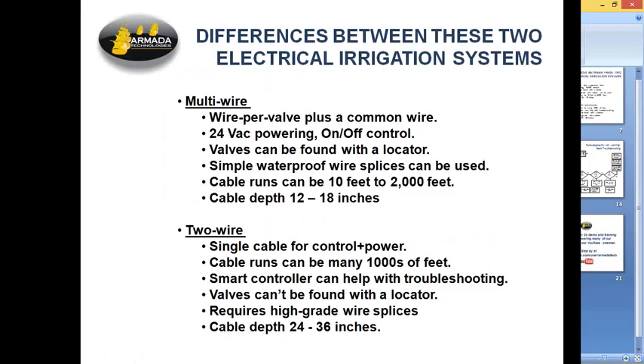The multi-wire turns on valves with a shot of 24 volts AC, and the two-wire systems commonly have something over 30 volts running on their control cable, and that voltage is led out to the valve to close the valve based on the command to a decoder. So literally, when you start working on two-wire systems, you're becoming a computer technician, having to troubleshoot the computer system and data communications and the slaves. So in that regard, it's somewhat different.